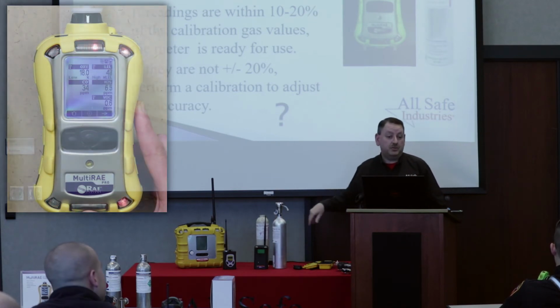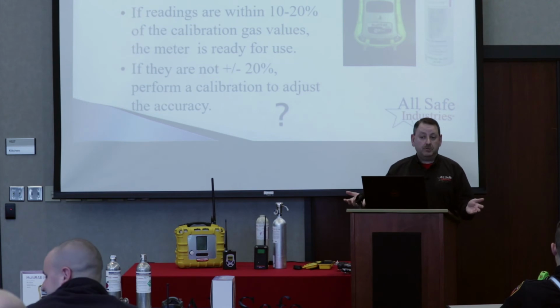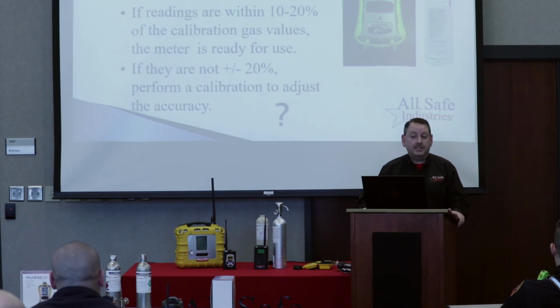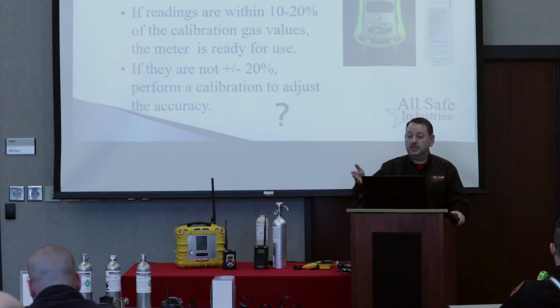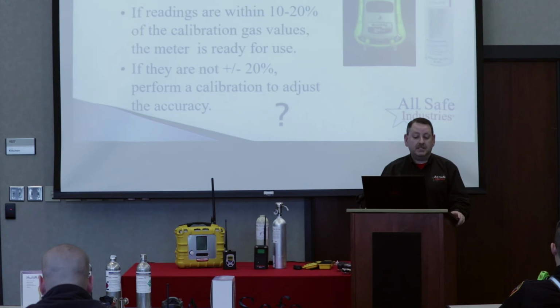It's called a bump check, and all the manufacturers recommend that you do a bump check before each day's use. Now, I know you guys, first responder world, you're not necessarily going to get up every day and want to bump your meters, but you've done this long enough, you kind of know when you're on a run where gas detection is going to be involved. And so when you get there on scene, that's when you can run the bump check, whether that's because your AutoRae 2 cradles are installed in the rig or you have a cylinder of gas that's going to allow you to do that bump check. Again, it's the best way to know that the meter's working properly.